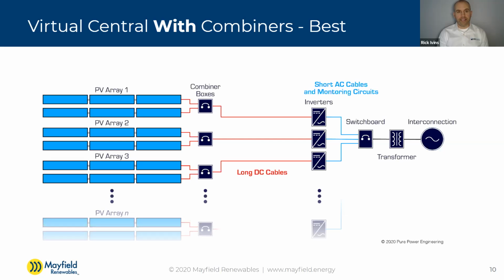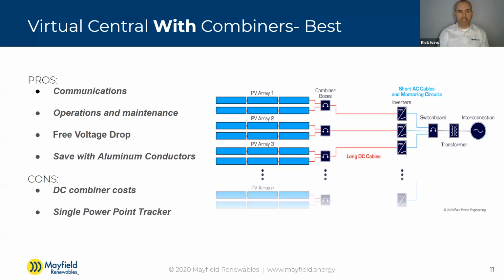Some of the pros and cons to this one: it's got some of the same pros as the previous design. Communications are still easy to install because the inverters are at that single pad. O&M can also be easier, though not quite as much as when you have all the string level testing at the inverters. You still have a little bit you've got to go out to the combiner boxes for, but you don't replace combiner boxes often. String inverters are much more frequent, so being able to access those with your vehicle easier, and having them more centralized for most of your maintenance, is still easier.